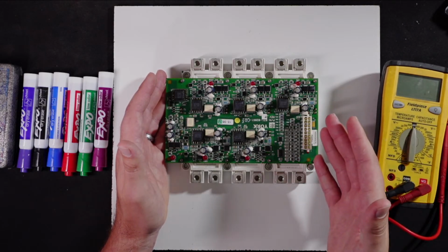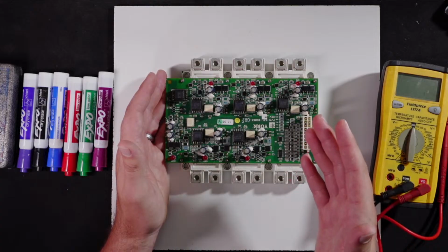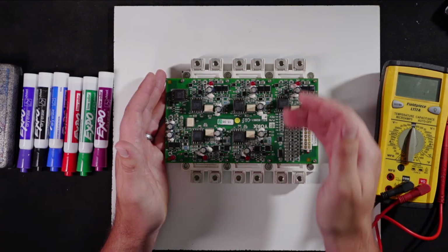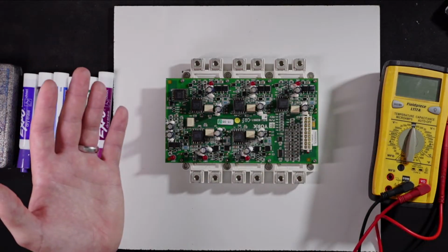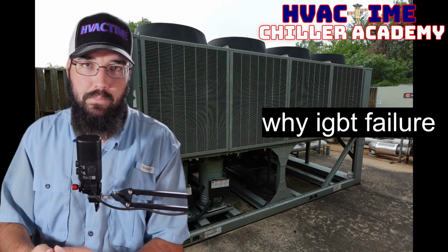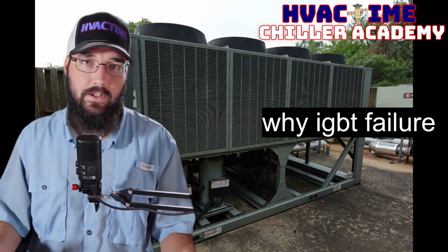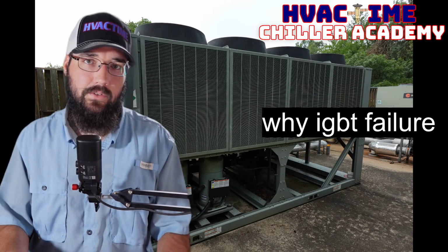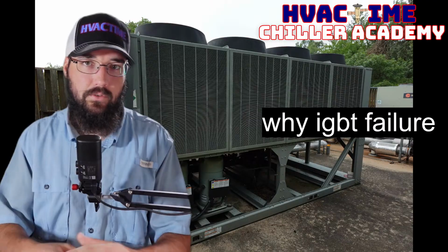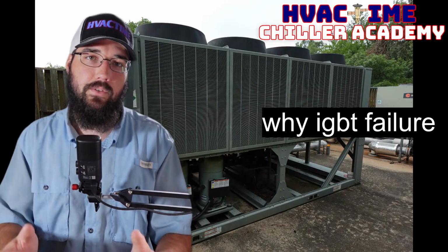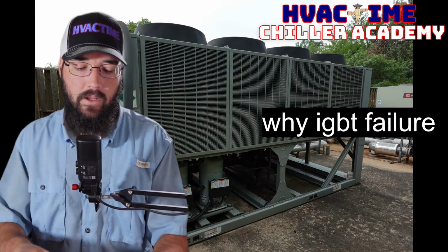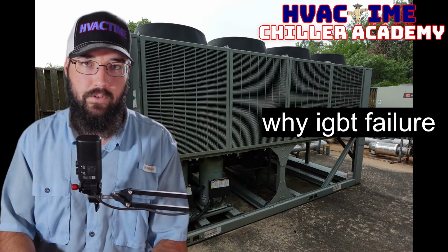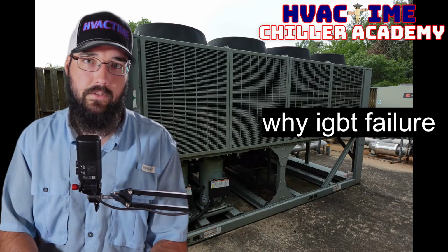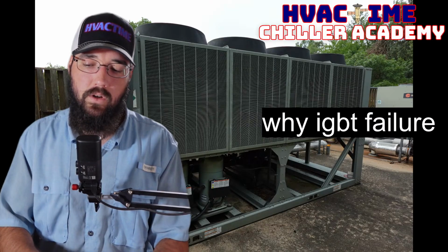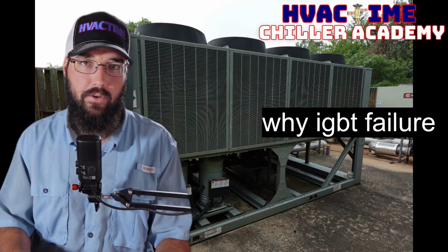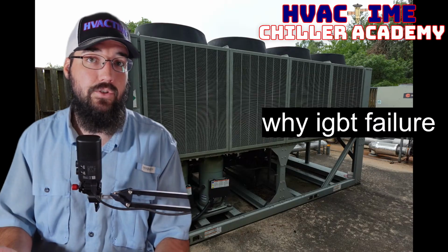There's no way to avoid that. There's nothing we can do to prevent that from happening. So at that point, we just have to diagnose it and replace it. It's just like a lot of other things. These components aren't built to last absolutely forever, so they're going to have failure points. Just the condenser fan motor, bearings, all of these are components that fail with wear and tear. The silicon components are no different. Absolutely no different. So it doesn't mean that there was a source of cause for the failure, versus it could have just aged and worn out.